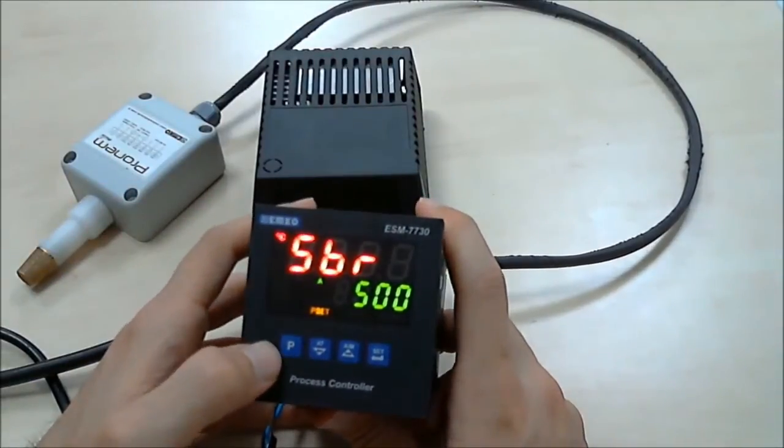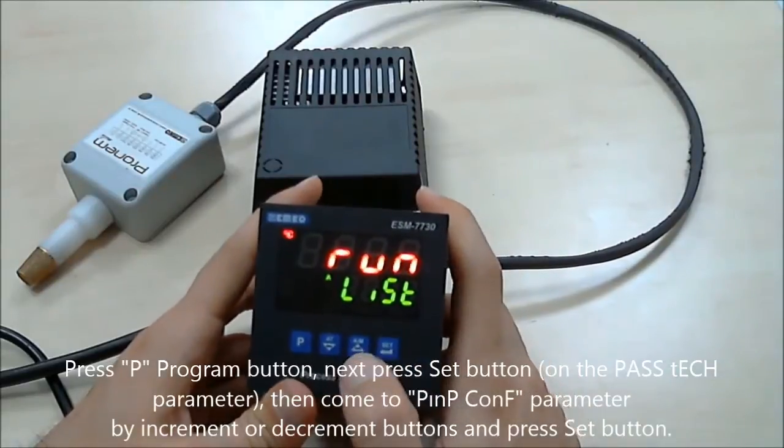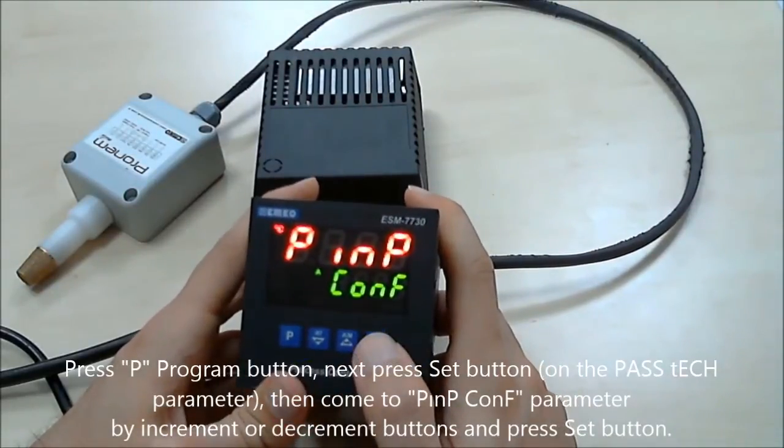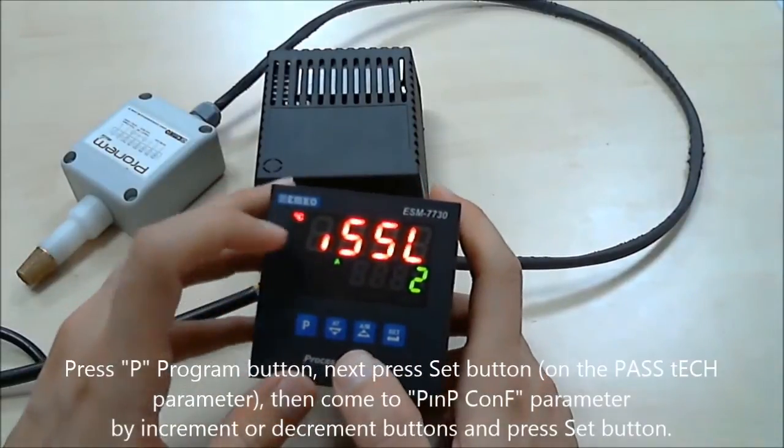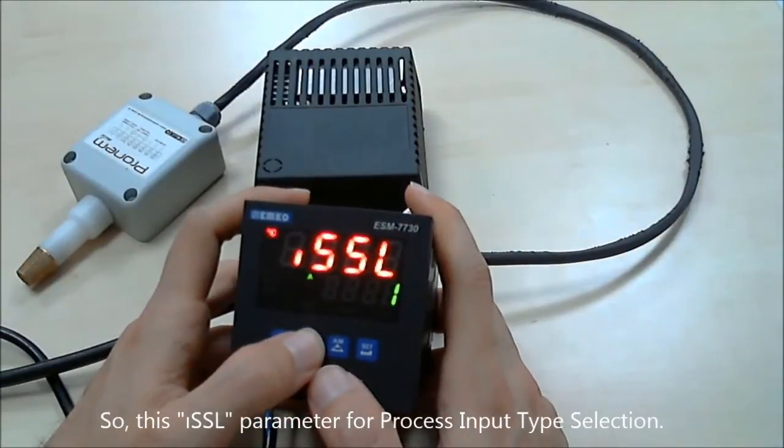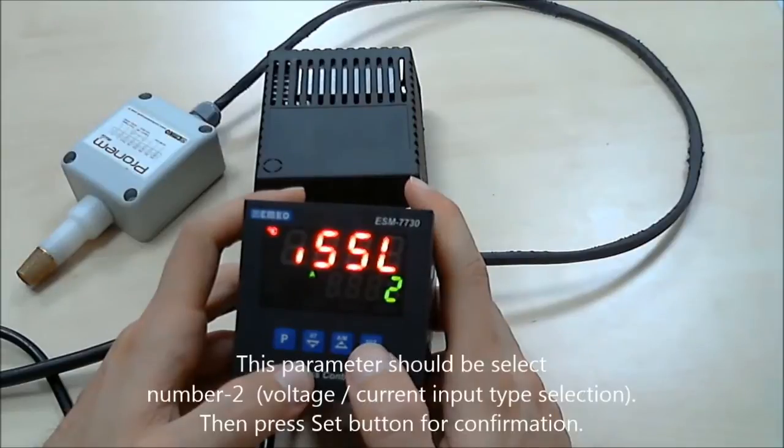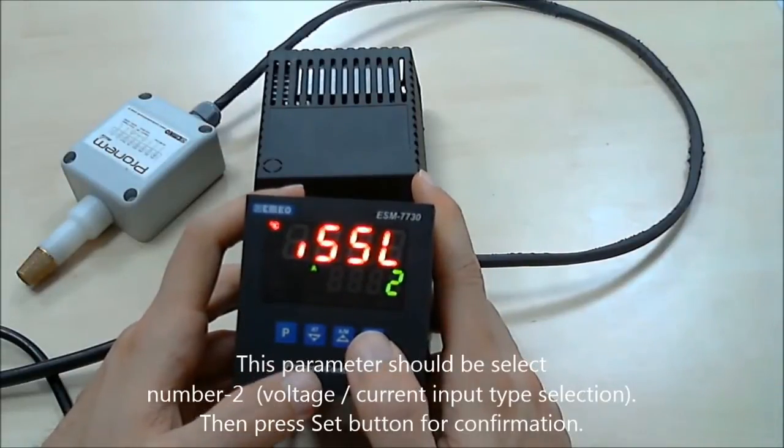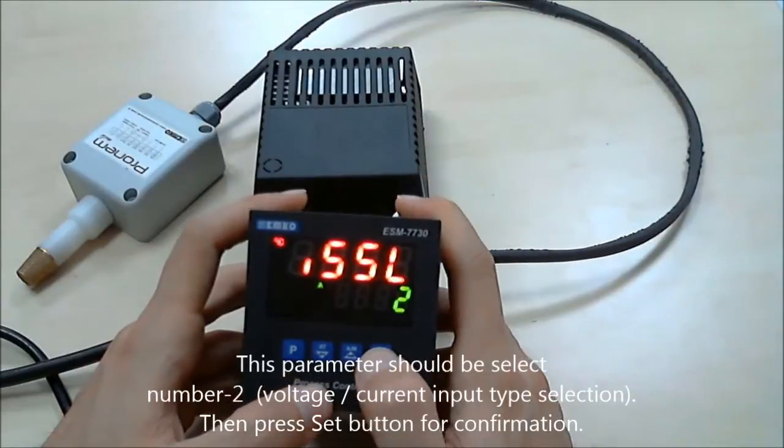Press the program button and press set button. Using increment or decrement buttons, come to the P input configuration parameter. This parameter is for process input type selection. This should be selected as number 2. Number 2 is for voltage current input type selection. Press set button for confirmation.